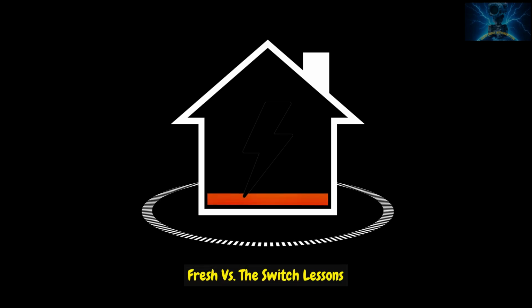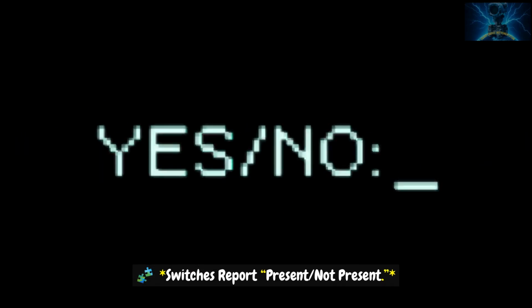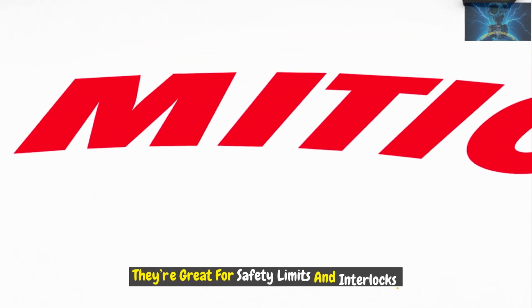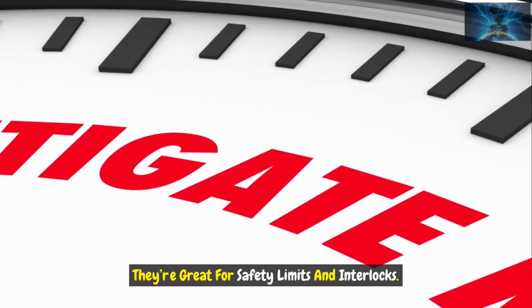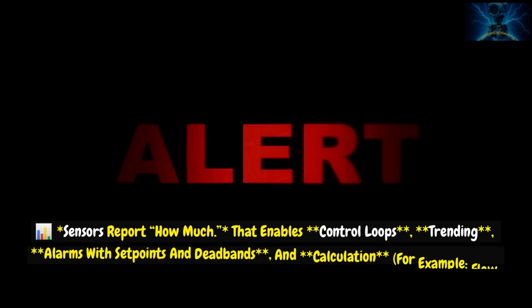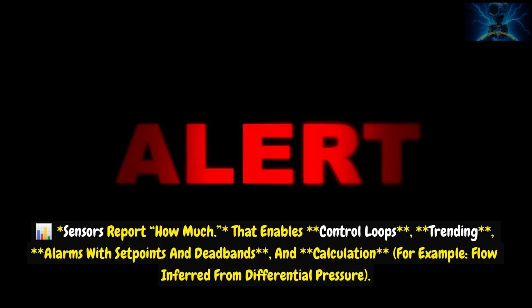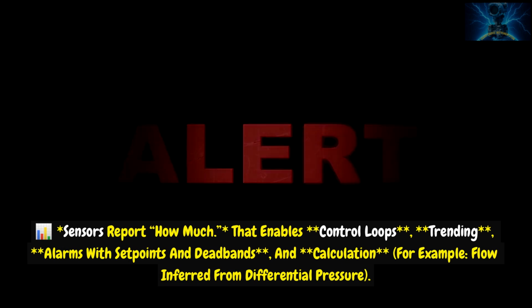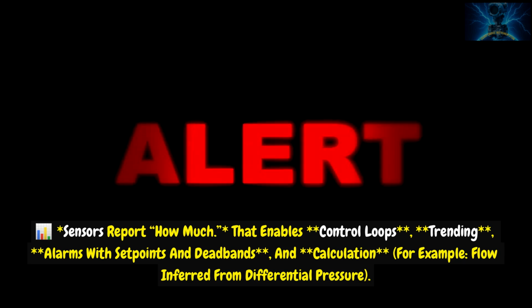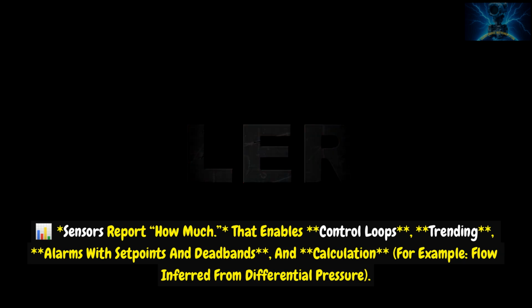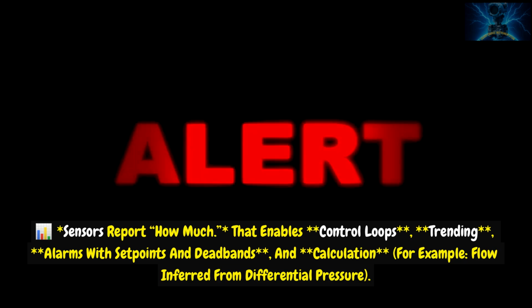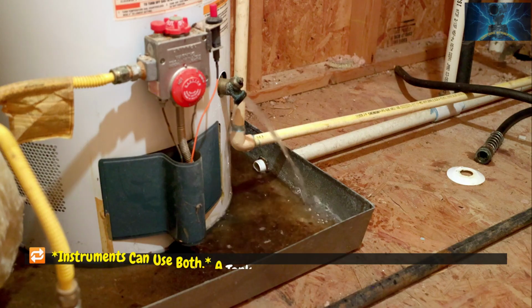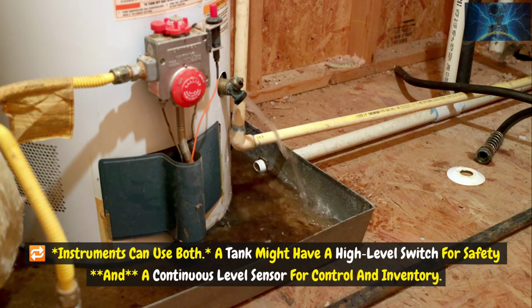Versus the switch lessons, why this isn't a repeat. Switches report present, not present. They're great for safety limits and interlocks. Sensors report how much. That enables control loops, trending, alarms with set points and deadbands, and calculation. For example, flow inferred from differential pressure. Instruments can use both. A tank might have a high-level switch for safety, and a continuous level sensor for control and inventory.